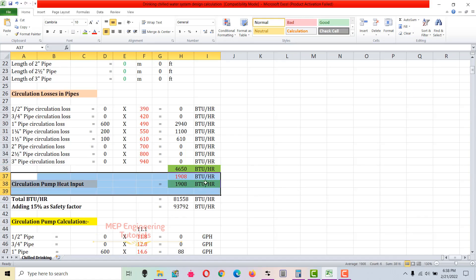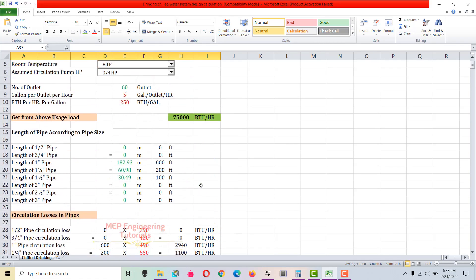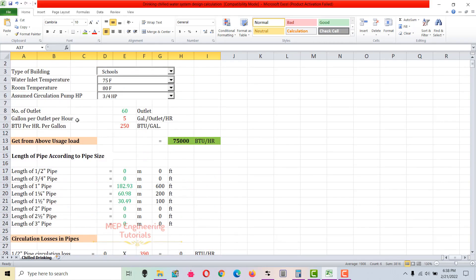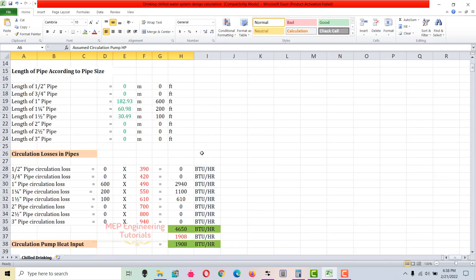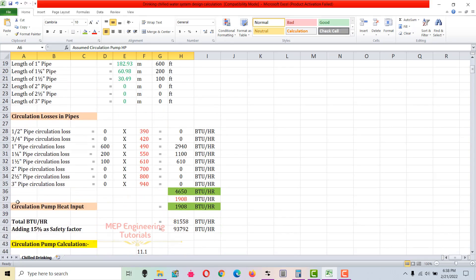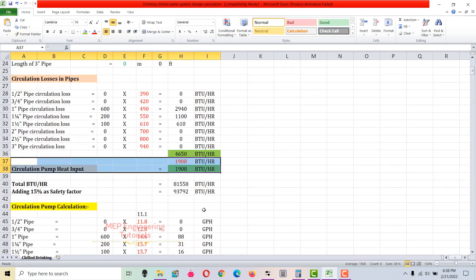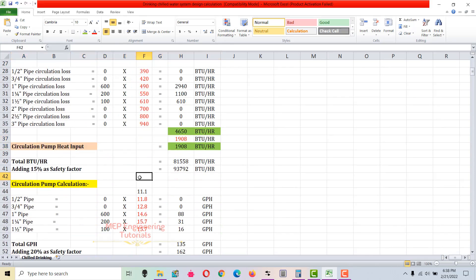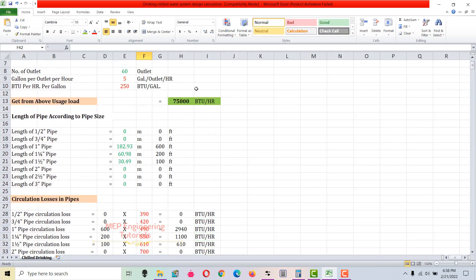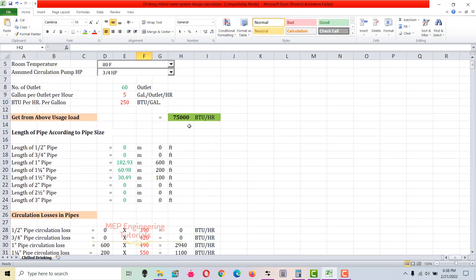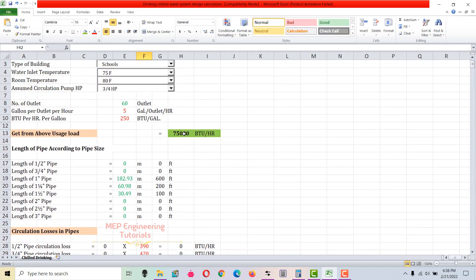The third item to calculate is the circulation pump heat input, which depends on the horsepower assumed. With 3/4 HP, the circulation pump heat input is 1,908 BTUs per hour.